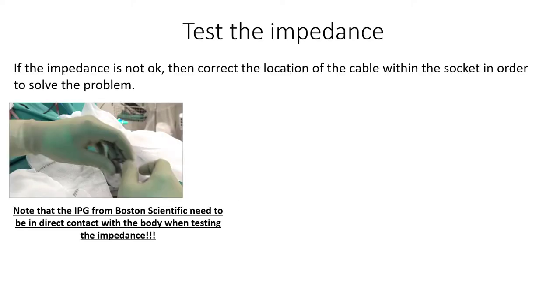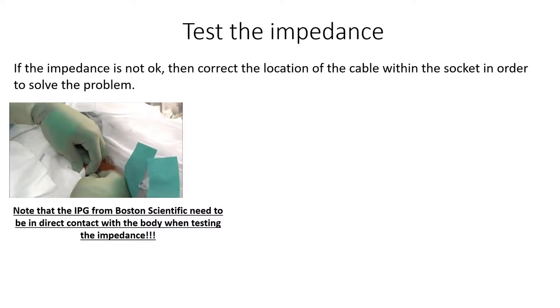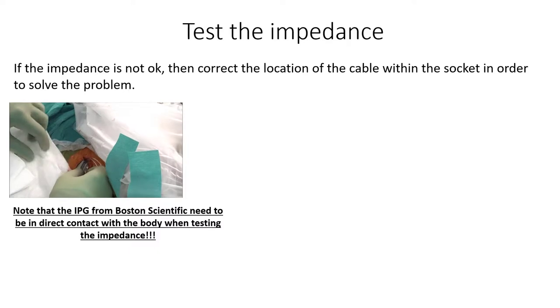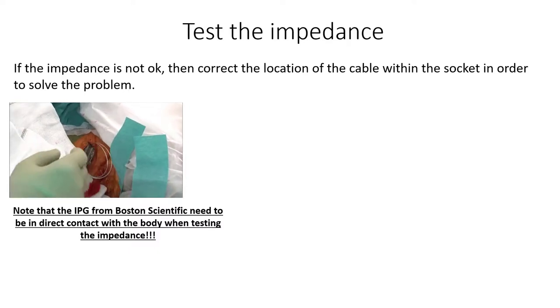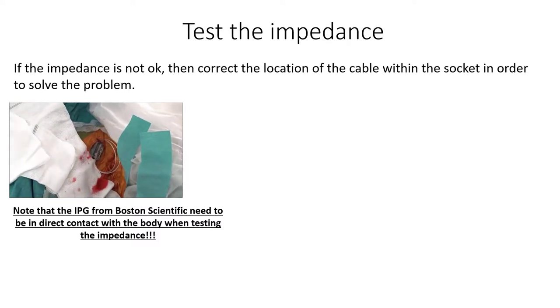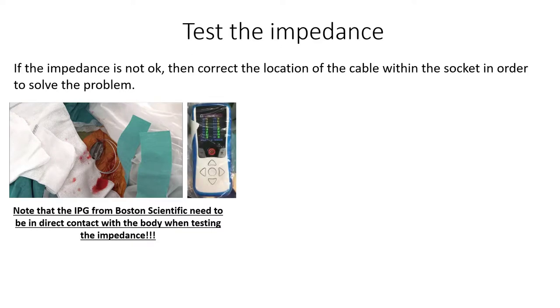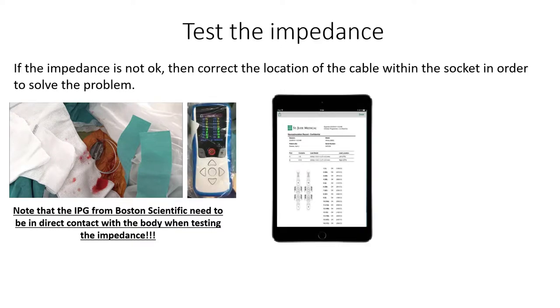Also remember to use the dedicated plug to seal the other socket on the IPG if you have only one extension cable or a double adapter using only one of the sockets. So, as I mentioned, we test the impedance after having tightened the lock screw. And note that the IPG from Boston Scientific needs to be in direct contact with the body when testing the impedance. The impedance is tested with the patient's remote control in Boston and with the patient programmer in Abbott.